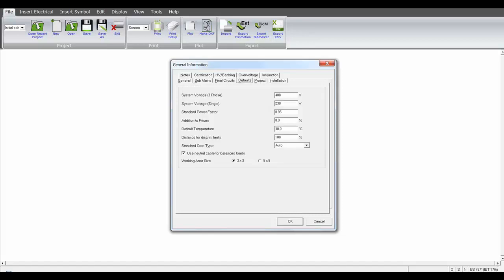There are default options you can apply in terms of your voltages, single and three phase, standard power factors, the size of the layout can be accounted for, and also whether you have balanced or unbalanced loads, the program will optimize the cable. So in this case, if you use the tick box, you use neutral cable for balanced loads, this will put a 4-core cable in irrespective of whether your cables are balanced or unbalanced. You can then make the appropriate decision here.